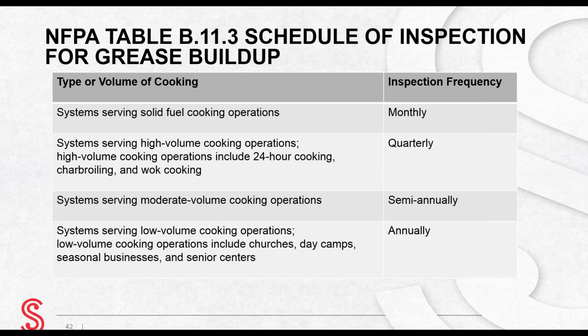This is NFPA's requirements on hood and duct inspection for commercial cooking. This can be found under NFPA 96. The exhaust system for meat smokers is treated just the same as any other commercial cooking appliance. The entire exhaust system, including the vent piping, shall be inspected for grease buildup by a properly trained, qualified, and certified person acceptable to the authority having jurisdiction and in accordance with the table shown on this slide.